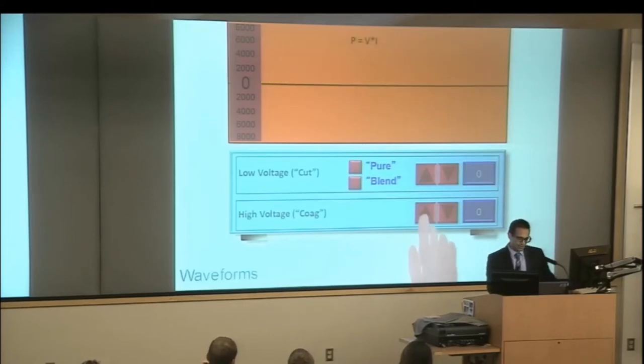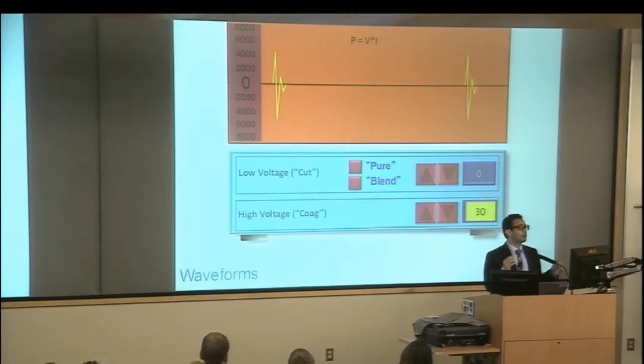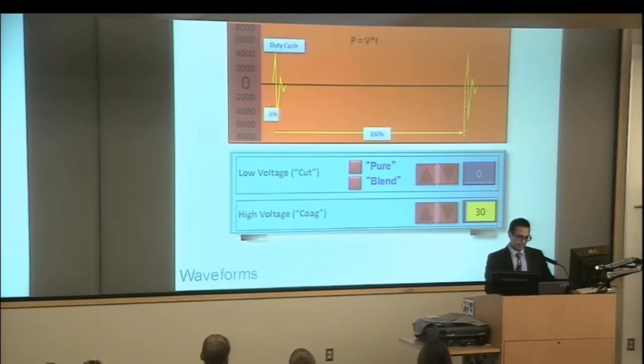Now let's contrast this to coag. You asked for coag 30. Again, it's 30, the same amount of energy per unit time, but now all that energy is concentrated in intermittent bursts of high voltage current. Current doesn't go through the circuit 100% of the time, it only comes at 6% of the time, so the duty cycle is 6%. Because of that, it's interrupted, much higher voltage, and a lower duty cycle.